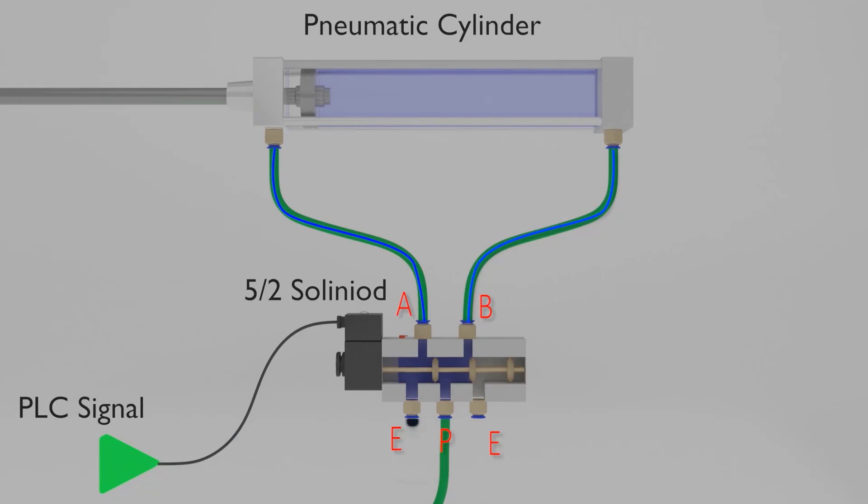Now when the PLC signal is turned off, it de-energizes the coil of solenoid valve. Its spool moves and links the pressure port with port A of solenoid valve and port B with exhaust port. This way the compressed air moves towards the port A and through pipe it enters the front port of the cylinder.